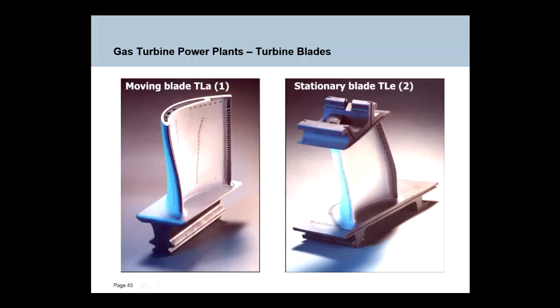In addition, the highest efficiency you get is a function of the higher combustion temperatures, okay? And what a modern gas turbine has is this very complex series of cooling holes, and there's cooling air blown through the blades so as to form a very thin layer of cooling air over the blades. The combustion temperatures in a modern gas turbine will be above the melting point of the metal in the blades. Okay? And it's only because the blades are cooled by this cooling air, and often they have some sort of ceramic coating as well, that they don't melt. So this is really high-tech stuff.